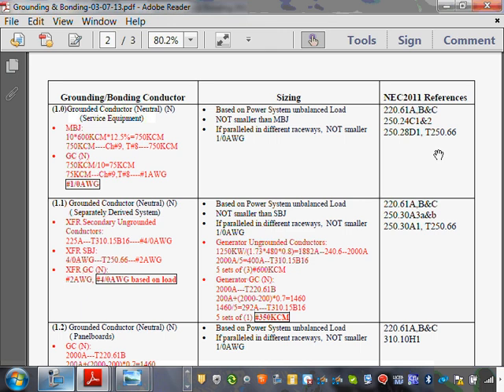And the first 200 amp, leave him alone. Anything higher than 200 amp, cut them by 0.7. So that's what we did. We cut it by 0.7, came up with this. Divide by 5 because I'm in parallel, and my neutral is 5 sets of 350 kcmil.